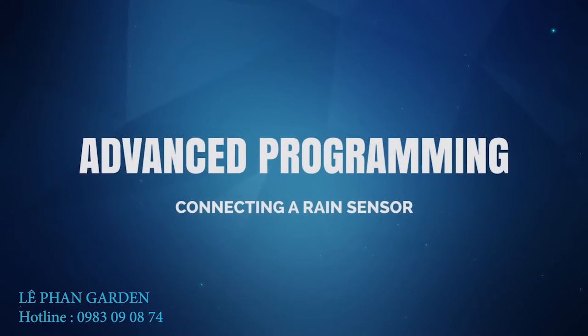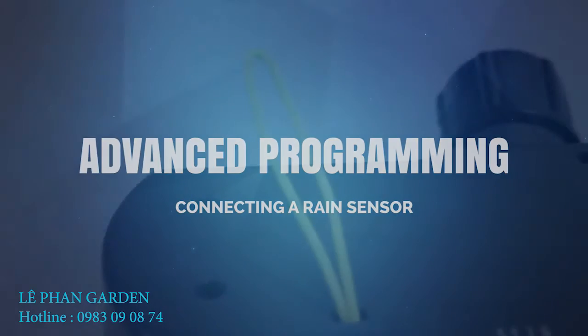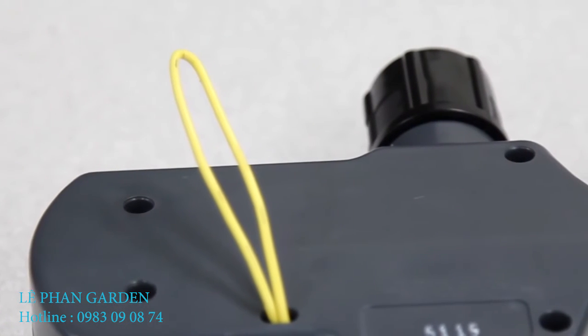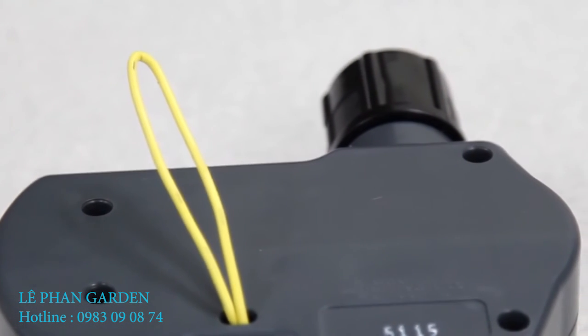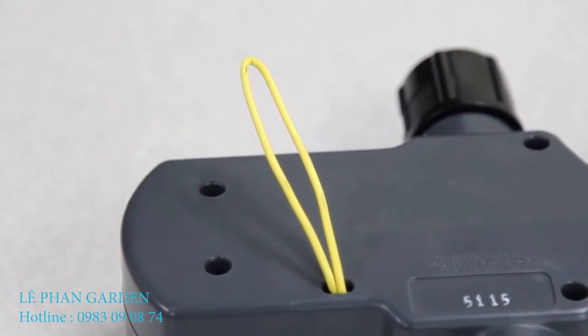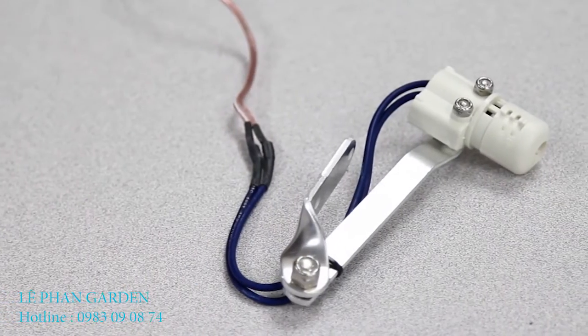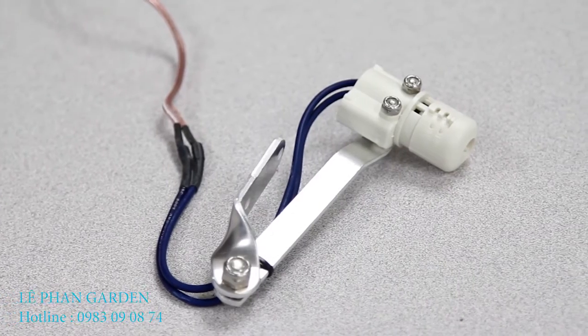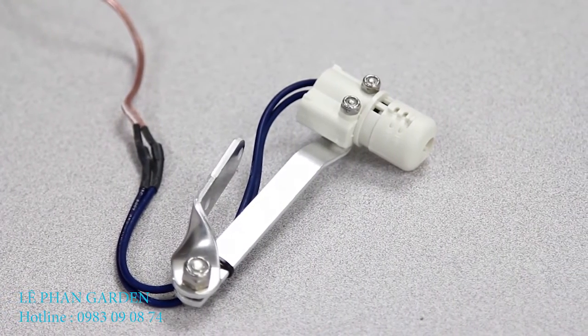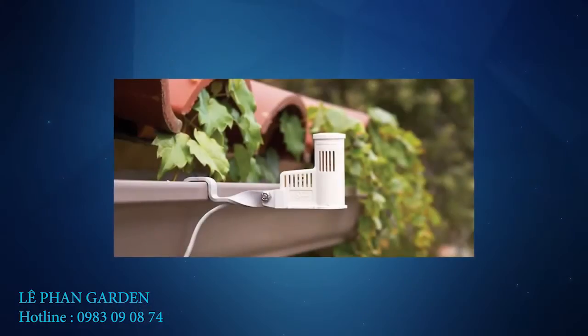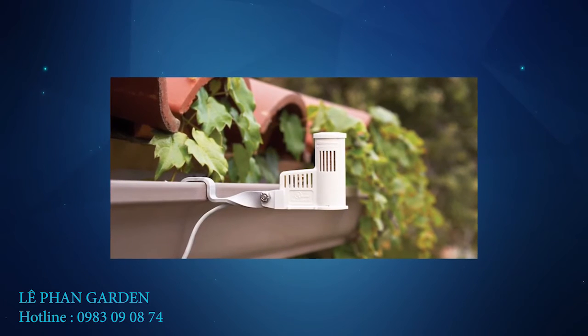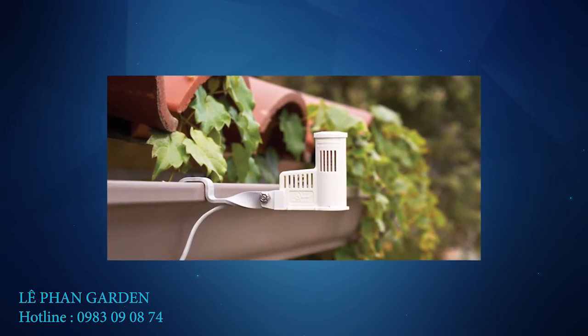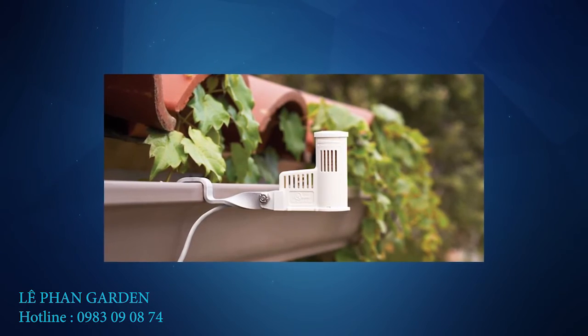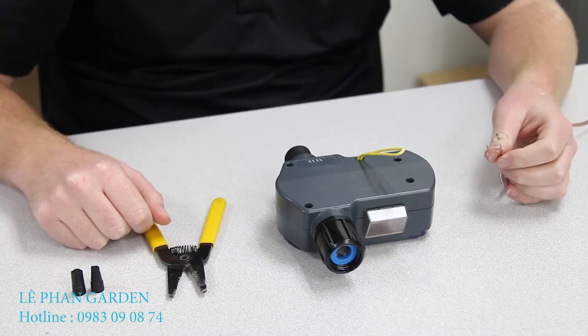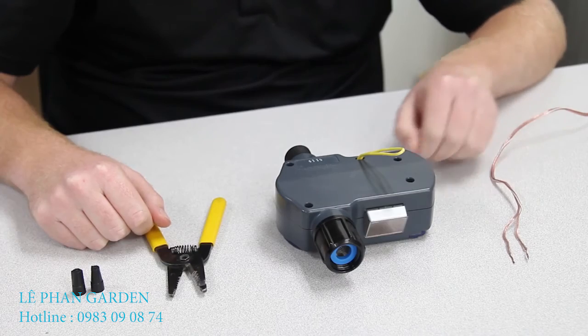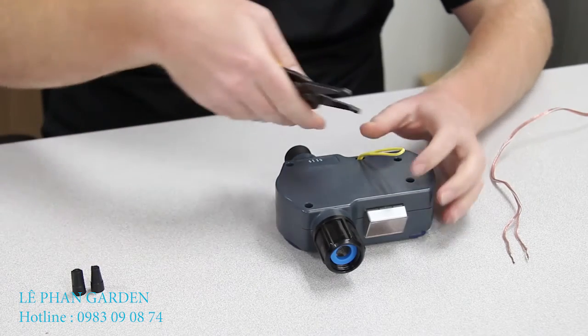The EVO 100 is equipped with a pair of yellow wires that can be used to connect a wired rain sensor so that the timer will not water by program after a user's set amount of rainfall occurs. Rain sensors are made by a variety of manufacturers and they are not difficult to install. To do so, mount the normally closed rain sensor to a roof eave or other uncovered location that will receive direct rainfall. Run the wires from the sensor down to the EVO 100 timer.